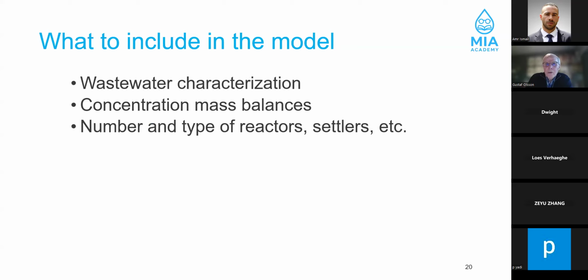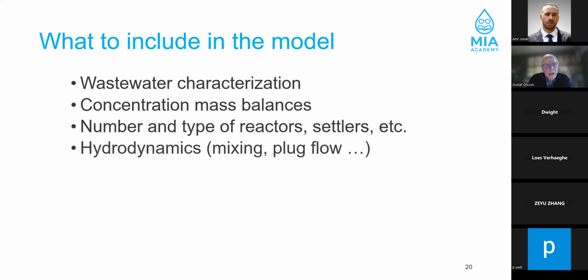In other words, are the reactors plug flow? Are they well mixed? Are they reactors in series and so on? That has to be recognized. The hydrodynamics of the reactors and of the settler is also important, because the settler is now sensitive to sudden disturbances in the flow rate. So the settler is hardly ever ideal. That has to be kept in mind.